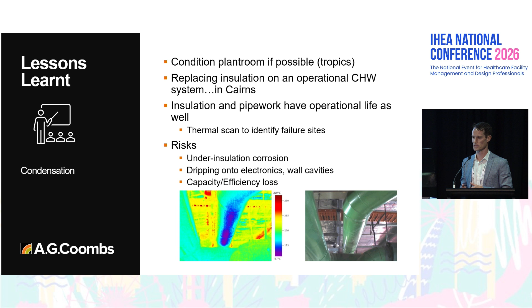Pipework and insulation have operational lives, so they're not going to last forever, and we need to start tracking or at least making observations about the condition of these assets over time. Non-destructive testing of some of the pipework systems is always a good idea. Maybe after 15 years, you do a 5-year sample of the worst case—coldest, highest, or lowest velocity areas—just to get a baseline for how your system is performing.